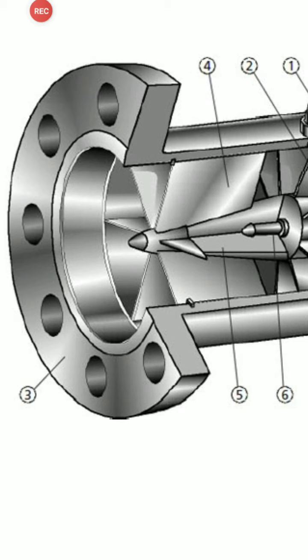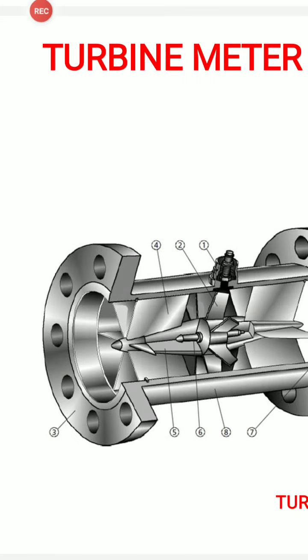So pipes are connected on the left and right flange. When the fluid moves, it glides over the vanes or blades of the rotor. The energy inside the fluid gets imparted to the blade when the fluid glides from inner section to outer section, it imparts its energy to the blade and ultimately it starts rotating.